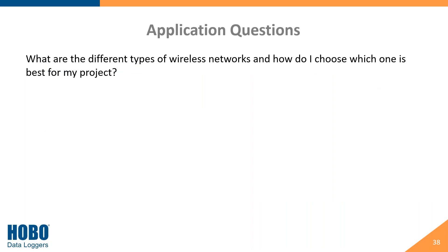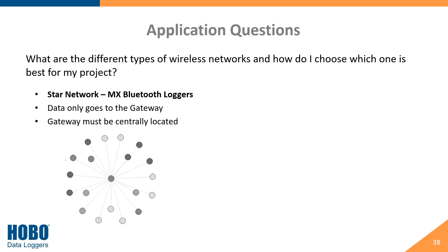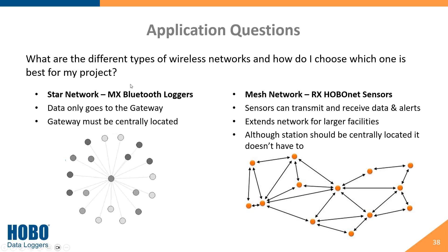What are the different types of wireless networks and how do I choose? Our MX Bluetooth data loggers with gateway use a star network — ideally with the gateway at the center and all loggers connecting directly to it. They can't pass signals through other sensors. Our HOBOnet wireless sensors, on the other hand, form a self-healing mesh network. While it's ideal to centrally locate the RX station, sensors can pass their signal through up to five other sensors in line to reach the station, making the mesh network more flexible for large or complex facilities.